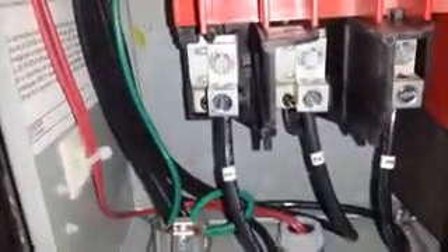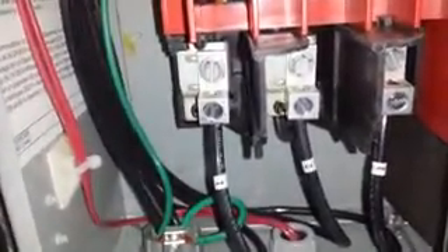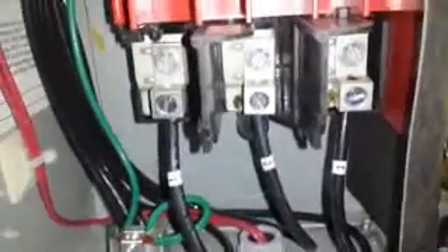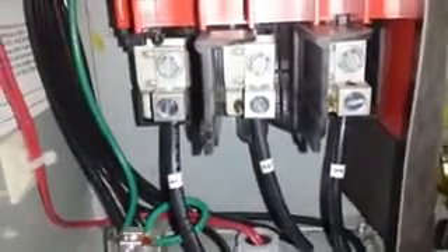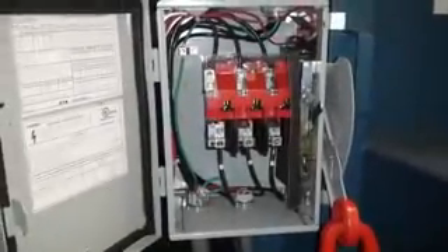What the simple drawing fails to show you is the correct order to the three-phase system, how it's usually set up. For starters, the disconnect is usually close to the motor, especially in modern buildings. Disconnects are located close to motors for safety reasons. Lucky for us, they also make troubleshooting easier. Let's start at the nearest disconnect. Before turning the disconnect off, turn the motor off. Never throw a disconnect under load.